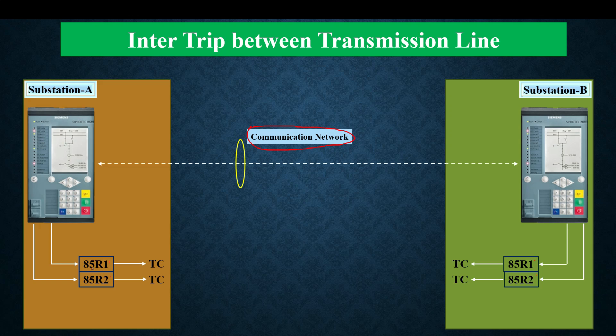The difference between these two tripping relays is that one is a high-speed trip relay and the other is a lockout trip relay. 85R1 can be considered equivalent to a 94 tripping relay, and 85R2 is a lockout relay such as an 86 relay. 85R1 is used for fast or instantaneous tripping, and 85R2 is used for delayed tripping.